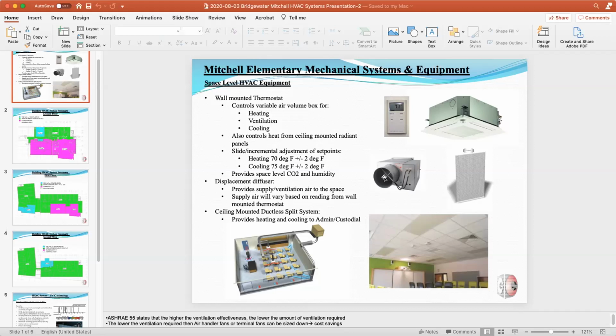That same thermostat or temperature sensor will also control the amount of hot water sent to a ceiling mounted radiant panel. So if we need supplemental heating that the air side system cannot provide, which will be the case in the winter heating season, that same sensor controls that. It'll have slide incremental adjustments. The design set points are heating at 70 degrees plus or minus 2, and cooling at 75 plus or minus 2. I'm going to follow up with a couple of slides after this and show the zoning of the rooftop units as well.